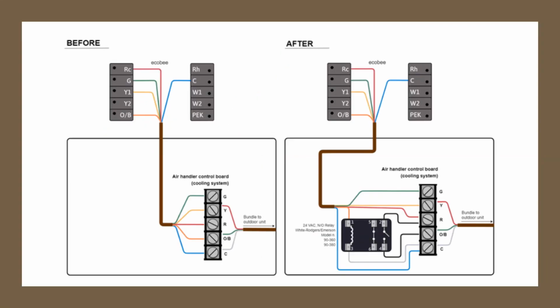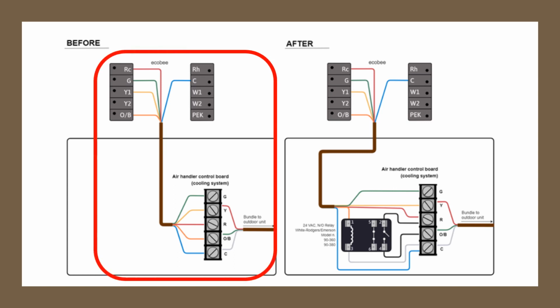This is a real-world case of an isolation relay being used on a thermostat to isolate one particular circuit. On the left-hand side, you have the wiring diagram that would normally apply to any air conditioning system or a heat pump. In this case, we have the green, the yellow, the red, the orange for the reversing valve, and the blue for the common. However, in this case, there were certain cases where the OB terminal was overheating on the thermostat because of high amp draw from the unit.